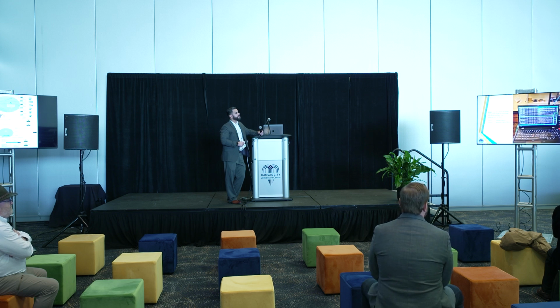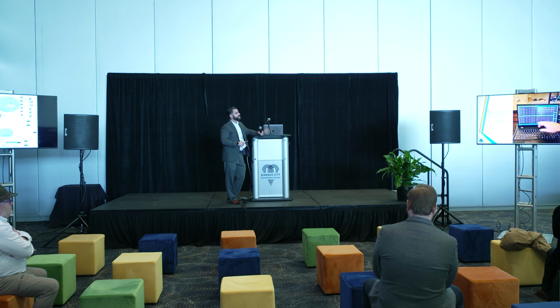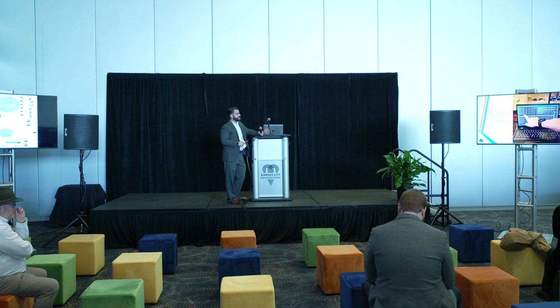So he's still talking. I'll go ahead and restore the cellular on Hub 1. And we should see that conversation resume shortly here. But note that we still have that flow of traffic being collected at the head end on Hub 2. So now we've restored. We see 10, which is the polling device behind the hub, reaching out to 1, and a full SCADA conversation occurring here. Right? Port 20,000 still flowing. And so we're back on both devices simultaneously.